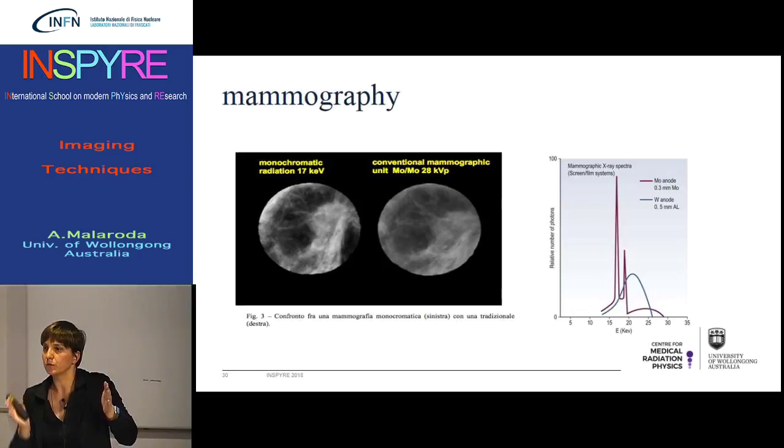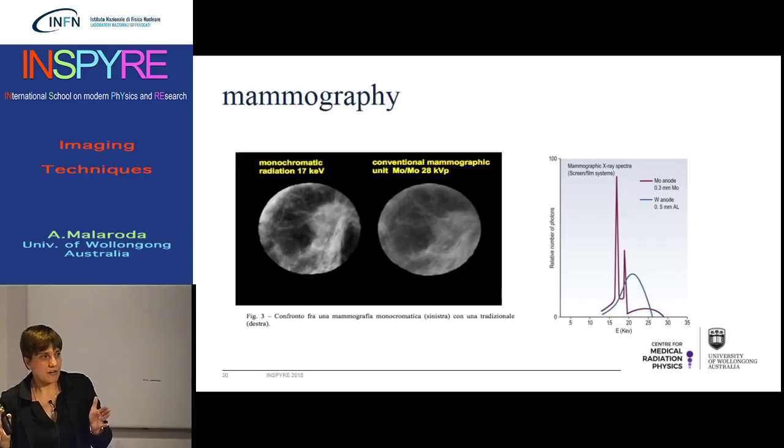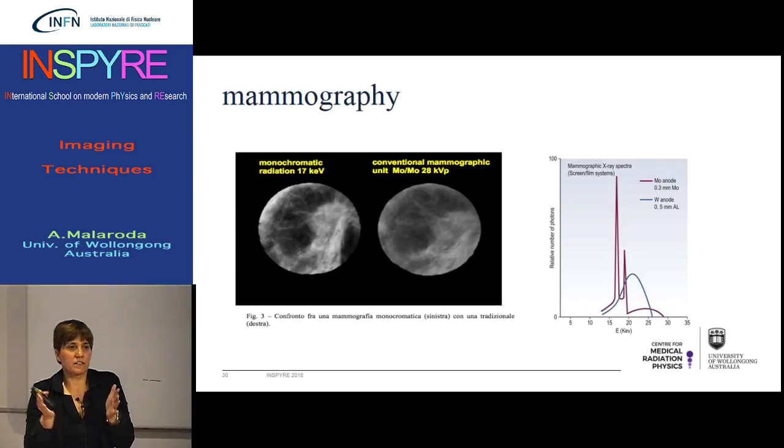And then you add another little filter of molybdenum. That little filter, the second Mo here, is going to cut more low energy photons and enhance the characteristic peaks. So if you've got an X-ray machine that gives you a range of energy, this is a way to try and make it as monoenergetic as you can.